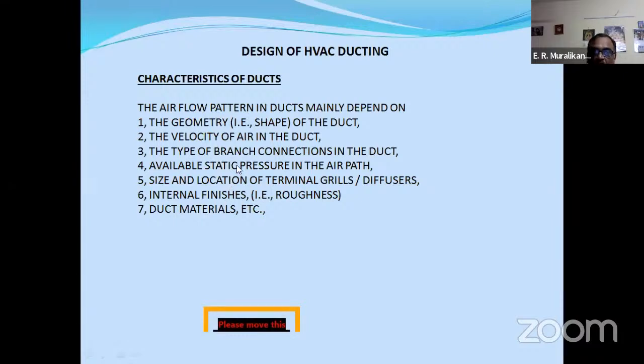When you have 120 GSM GA sheet or 240 GSM GA sheet, of course 240 GSM sheet will be a little heavier and a little costlier, but it has a better finish and lesser friction loss compared to 120 GSM GA sheet. But it is nowhere specified in the standards or any material what the friction is for this GA sheet. It's nowhere specified. It's only on assumptions that we go.